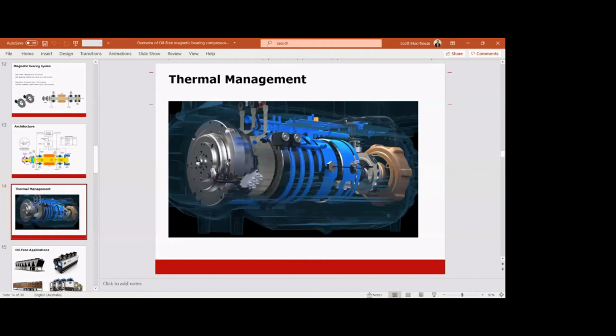Centrifugal uses kinetic energy to increase the pressure, where positive displacement physically takes the gas and squeezes it through a set of scroll plates or through a piston or through a rotor on a screw. And these forces on the bearings, when we're physically squeezing the gas, are extremely high, and magnetic forces could not handle these stresses. On a centrifugal, we just spin the impeller extremely fast and we induce the gas and then create a pressure difference using kinetic energy.